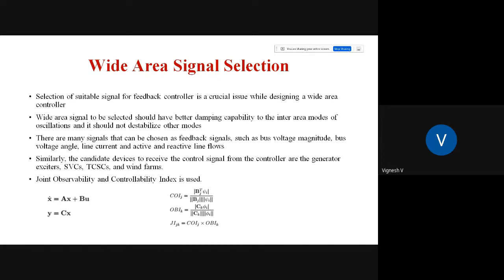Based on this index, we select which signal has the maximum information about the oscillation. For example, if there's an oscillation near Chennai, it doesn't make sense to use a signal from Meghalaya to damp it out, because you wouldn't observe the Chennai oscillation in a signal from Meghalaya. That's why this index is very important.